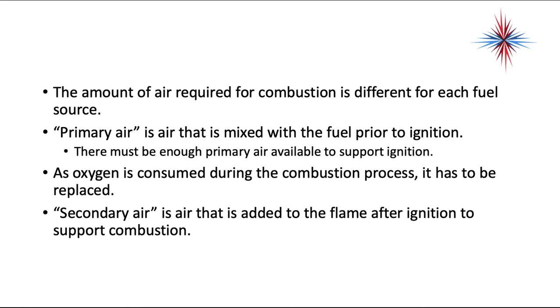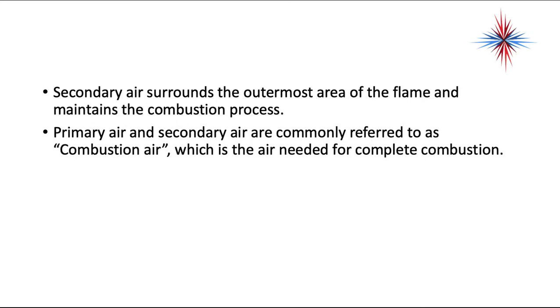The amount of air required for combustion is different for each fuel source. Primary air is the air that's mixed with the fuel prior to ignition — there must be enough primary air available to support ignition. As oxygen is consumed during combustion, it has to be replaced. Secondary air is the air added to the flame after ignition to support combustion. Secondary air surrounds the outermost areas of the flame and maintains the combustion process. Primary air and secondary air are commonly referred to as combustion air.